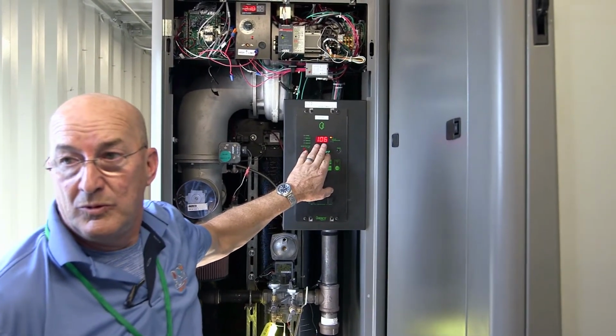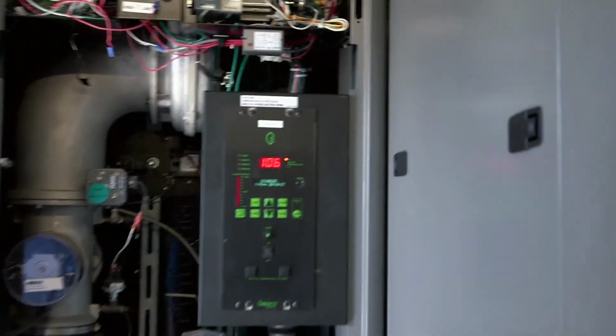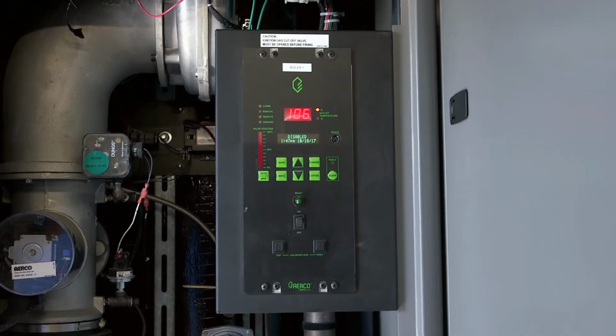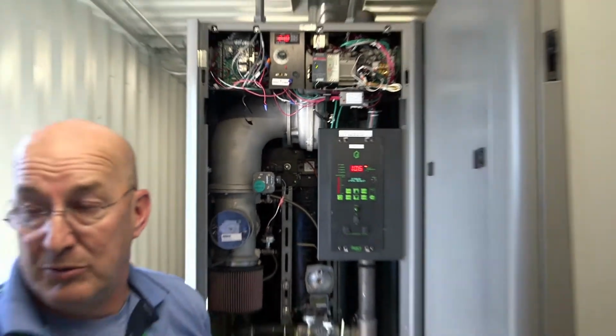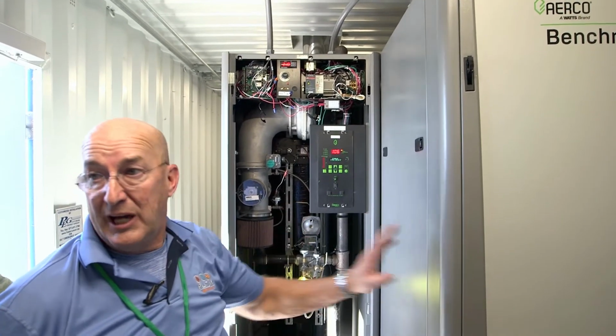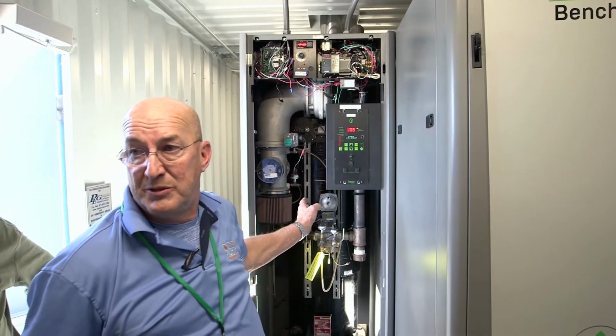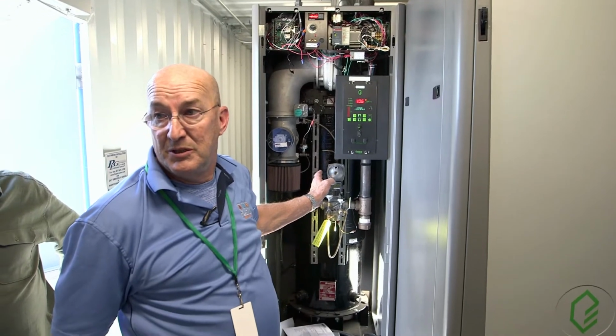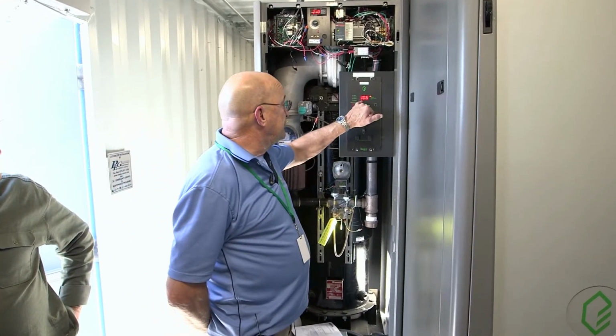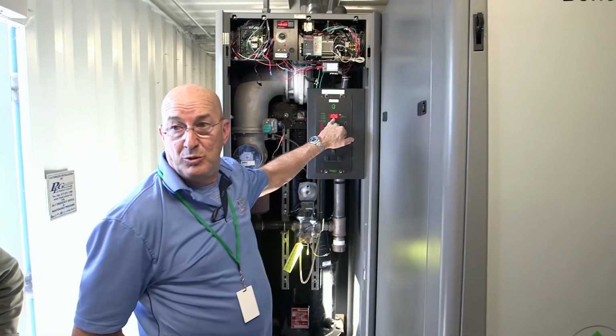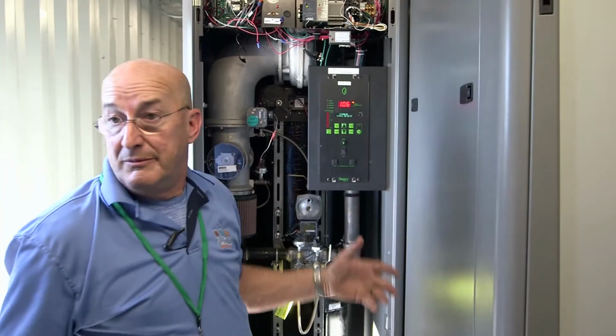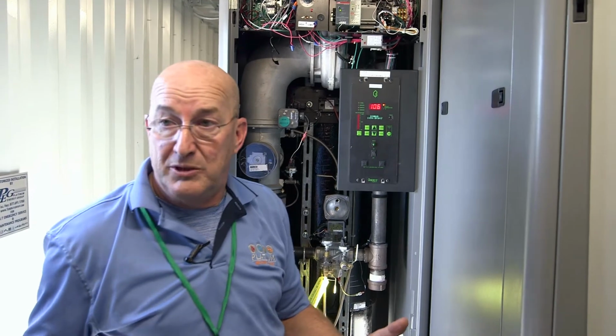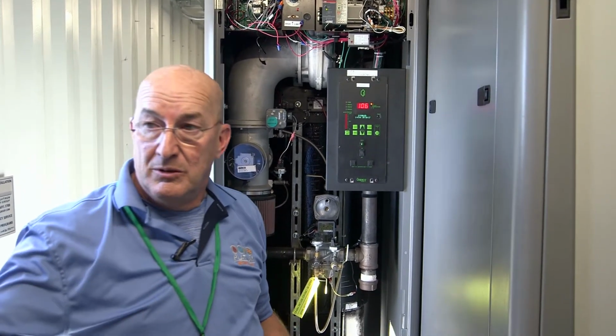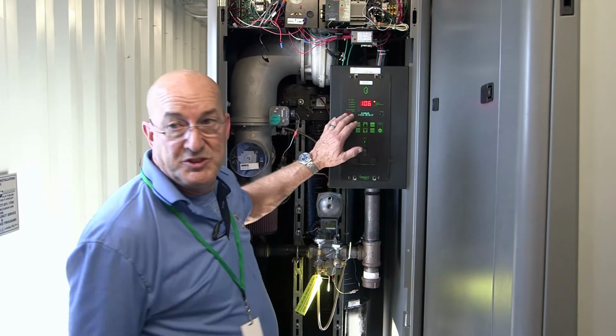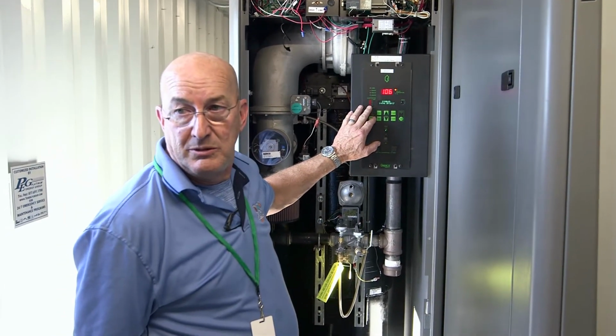Now, what about if that happens? Can I switch over to this one right away? It'll switch over on its own, automatically, to the other boiler, and run on the other boiler, so you'll have heat. You'll just know you have a problem with this boiler, and you're going to have to call for service to get this boiler serviced. The actual water temperature is displayed here, so you know what the temperature is at all times. We'll get to that in a minute, but there's a remote setup that you can use to find out what everything's doing.